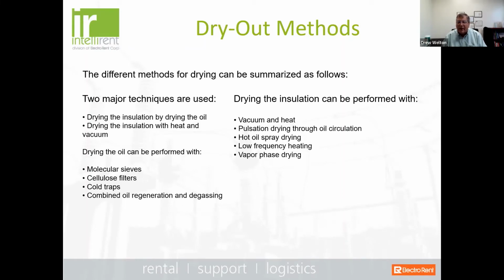The problem with trying to do that on an aged transformer is it can actually cause more problems than it can solve. You can actually destroy the older insulation by trying to do this after the transformer's been in service for many years. So what people do is they can perform a vacuum and heat, they can use hot oil spray drying, or bring up a truck and do an oil exchange. But the problem with this is that you're pulling the moisture out of the oil and not the insulation. And if the transformer is offline, remember that moisture goes from the oil back into the insulation. So you're doing your best to dry out the insulation using the oil. So we'll heat the oil up.